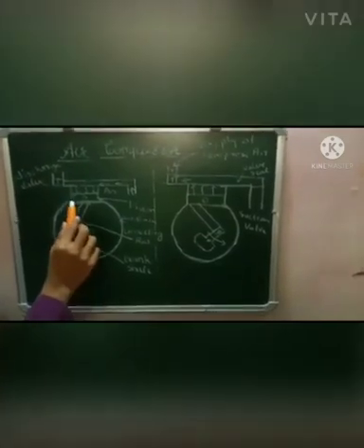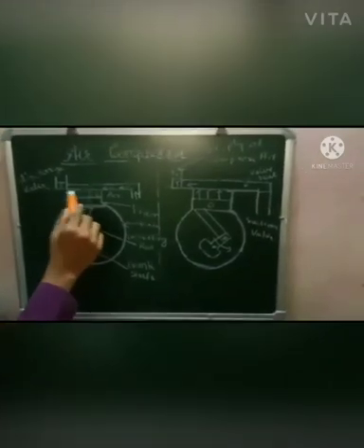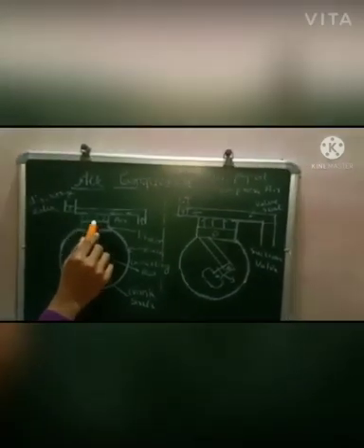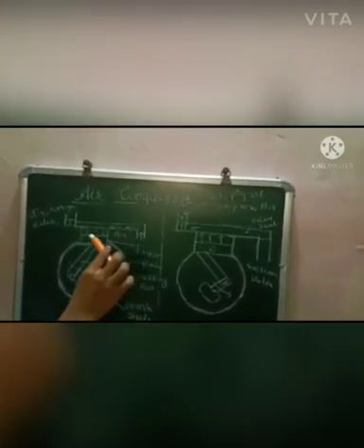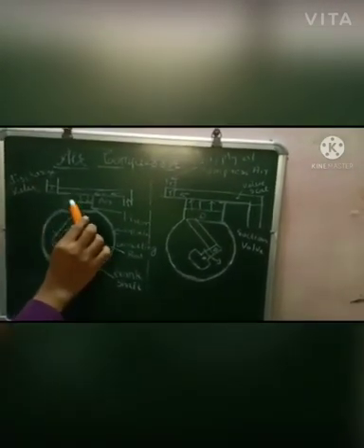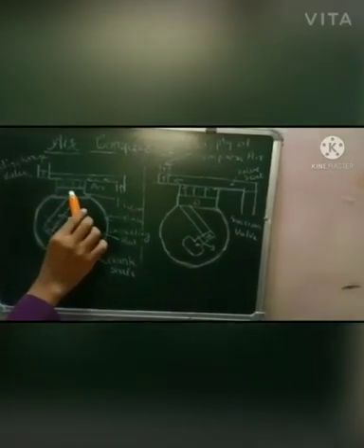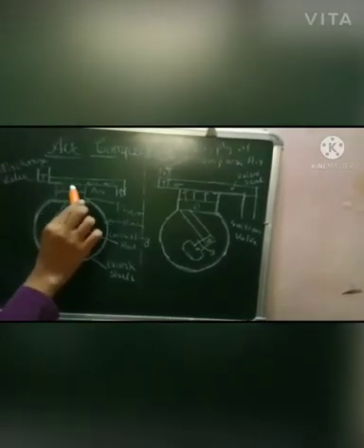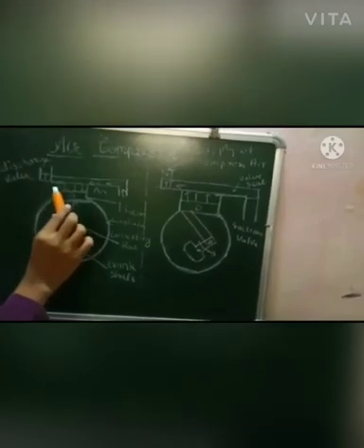And the piston inside the air compressor moves downwards and it creates a vacuum above the piston, which creates suction in the suction valve, and incoming air comes inside the air compressor and the discharge valve gets stopped. This happens because atmospheric pressure is greater than the vacuum inside the air compressor.